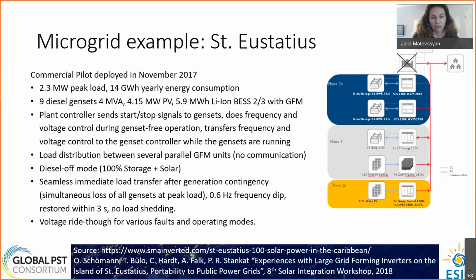There is seamless immediate load transfer after generation contingency, and a contingency has happened where an entire genset was lost and frequency dipped 0.6 hertz. The frequency was restored within 3 seconds, and no load shedding was necessary. Also, voltage ride-through for various faults was tested during operation. So this is one of the examples of successful deployment of a grid-forming battery in an island application.